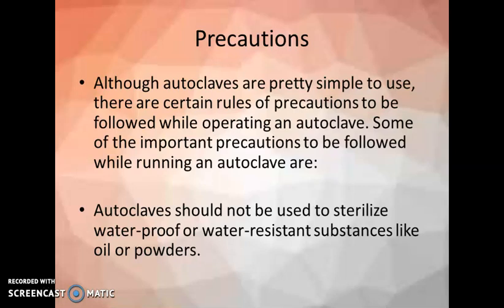Next, we should remember about the precautions. Although autoclaves are pretty simple to use, there are certain rules of precaution to be followed while operating an autoclave. Some of the important precautions we should follow while running an autoclave are: autoclaves should not be used to sterilize waterproof or water resistant substances like oil or powders, because they might not get wet, and these oils or powders are usually sterilized using a hot air oven.